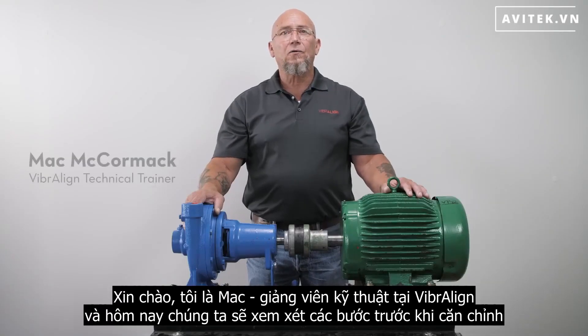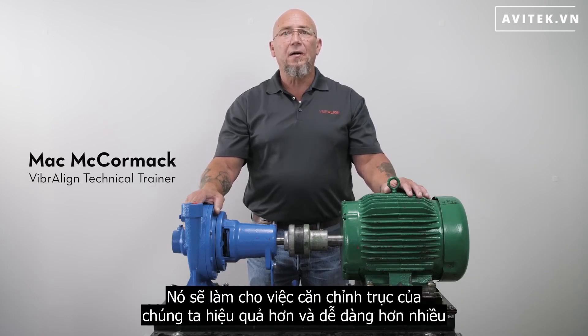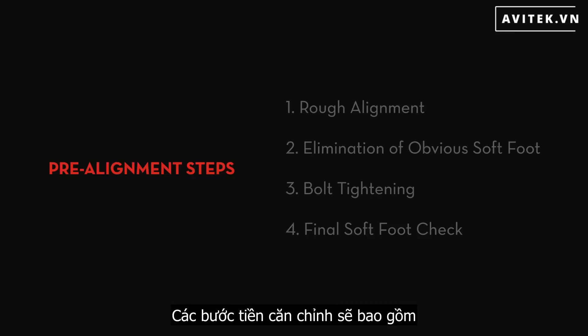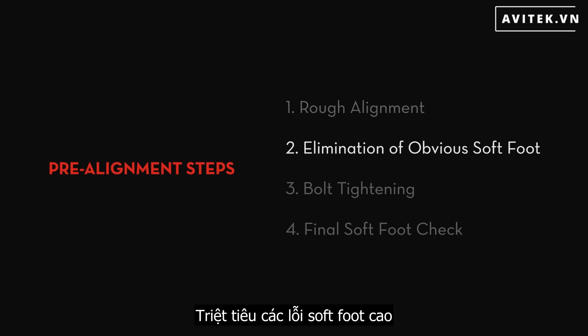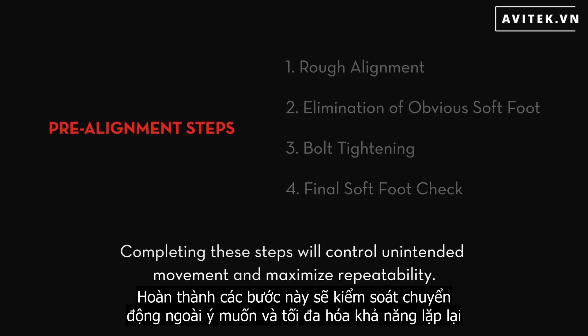Hi, I'm Mac, technical trainer at VibrAlign, and today we're going to go over four pre-alignment steps that will make our shaft alignment much more efficient and much easier. The pre-alignment steps we'll cover are rough alignment, elimination of obvious soft foot, bolt tightening, and final soft foot check. Completing these steps will control unintended movement and maximize repeatability.